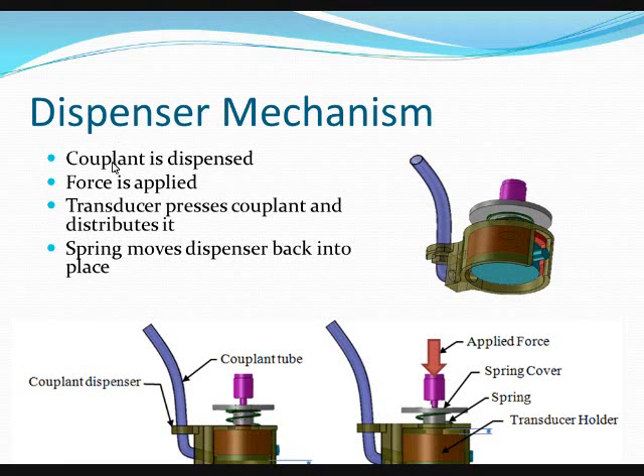The dispenser mechanism works by first dispensing the couplant through a tube into the couplant dispenser. Once inside the couplant dispenser, an additional force is applied onto the system, which presses down upon this coupler, the spring cover, and the transducer. And then what that does is it presses down, forcing the couplant to spread around on the bottom of the surface, and any excess couplant goes outside of the system. Once the system is done performing a test, the spring moves the system back into place.